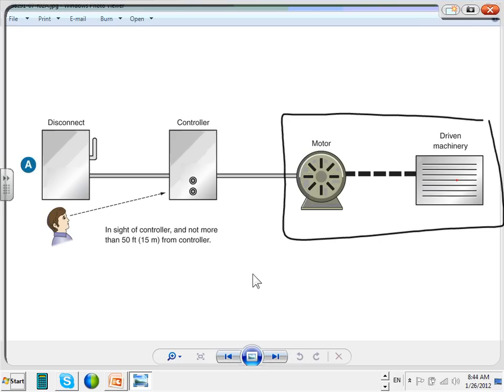Now, a lot of the time, guys, these are all in one, right? If you have an air handling unit, you're going to find the air handling unit machine that you're driving, as well as the motor, as well as the controller, all in one big box. Great, but it doesn't have to be. It could be in one big box, or it could be in different boxes. If they're different boxes, then the disconnect has to be within sight of the three of them, or you have to have one disconnect for each one of them, believe it or not. Now, most of the time, people are smart enough to have one disconnect. Most of the time, guys, they will be right in one big enclosure, and we have one disconnect to disconnect all of them safely. Any question, guys, about that?